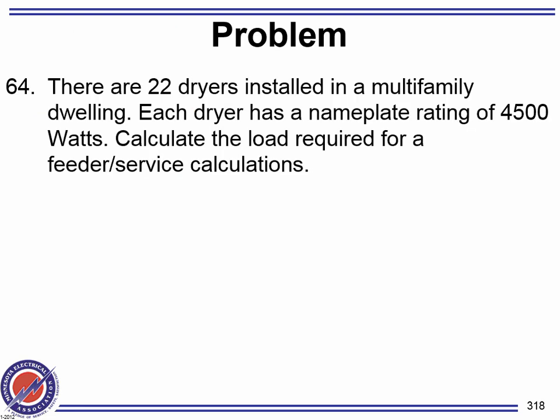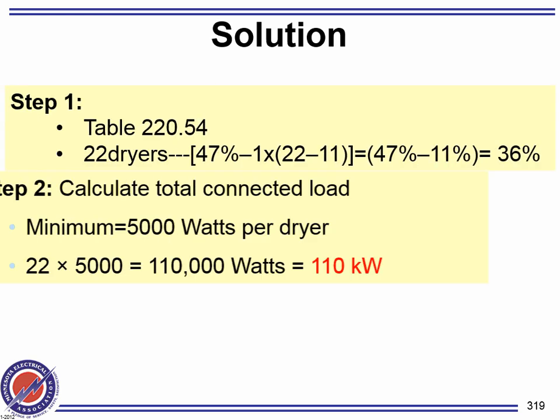Okay, there are 22 dryers. Speak of the devil. 22 dryers installed in a multi-family dwelling. Each one of them is 4,500 volt-amps. Calculate the load demand for feeders and service calculation. Okay, remember the 22. I have 4,500. So would I use 4,500 or 5,000? 5,000. Okay, there we go.